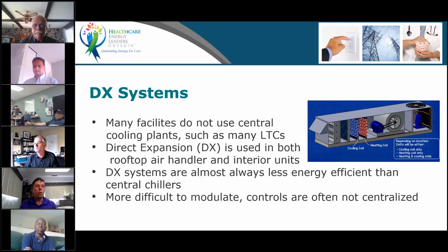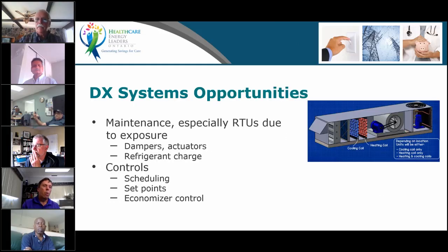So you may actually need to reopen those dampers when there's a high cooling load for the rest of the system that is not isolated if you have DX. So again, the DX, for those of you who are not familiar with that, that's direct expansion. So those are your standard rooftop units, for example. And they do need a certain airflow both for heating and cooling. And if you start playing around with the isolation damper, well, you may run into issues with the heating and cooling section. So always be aware of that.